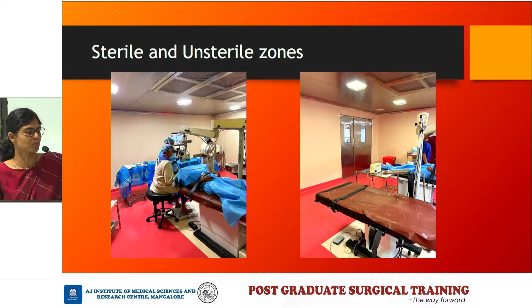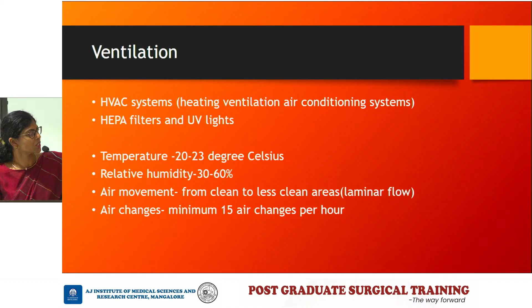Coming to ventilation, many OTs are fitted with HVAC systems, but some have split ACs, which need to be cleaned every month. What you need to observe is whether the temperature is maintained between 20 to 23 degrees Celsius, with relative humidity around 30 to 60%, and about 15 air changes per hour.